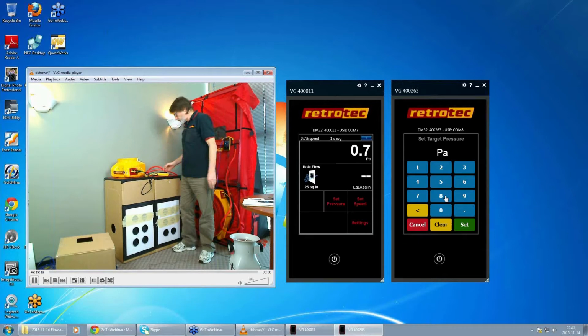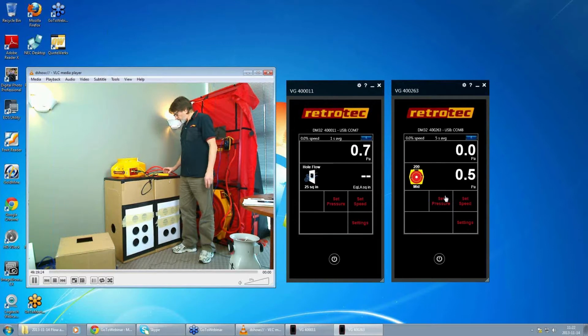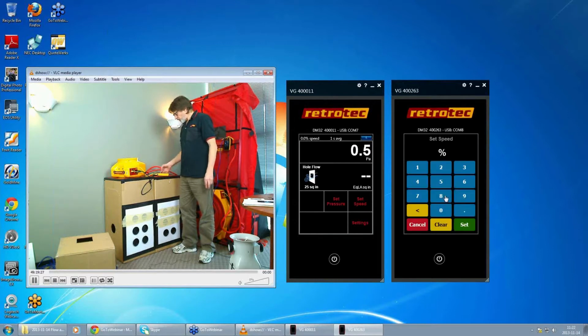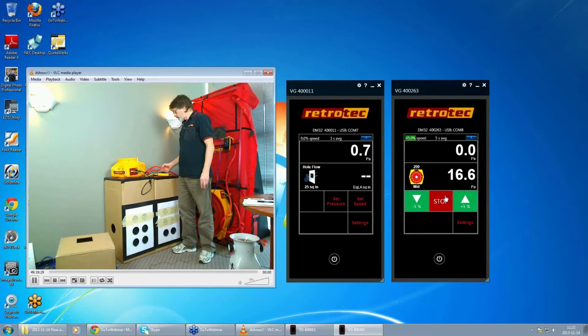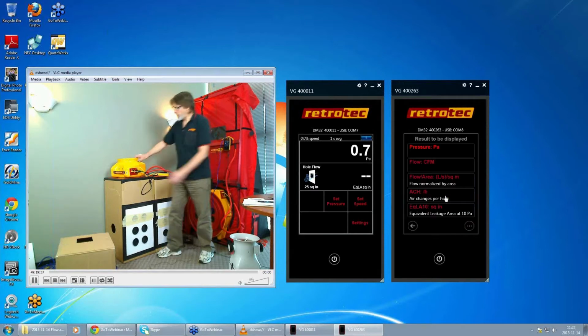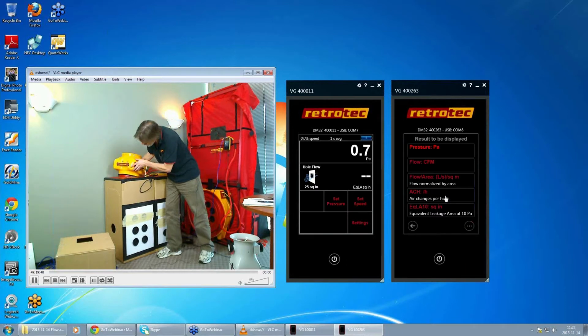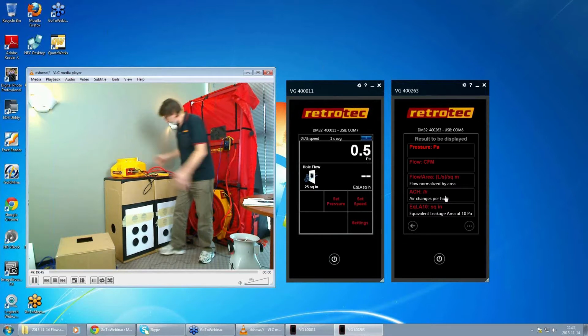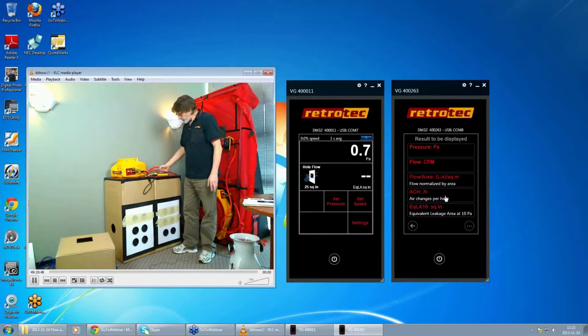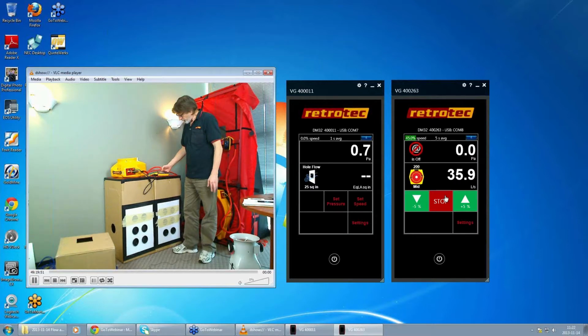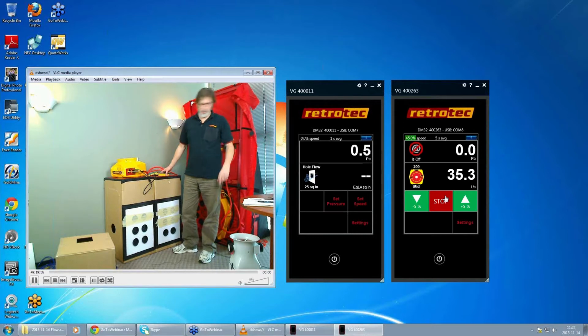Okay, so here I'm going to set the speed. I'm just going to set it to about 45%. And I'm going to change this to, you can't see this, but this duct tester here is on the mid-range. So it's going to plop it back in there. So I'm going to measure flow in CFM. I'm set to the mid-range on the right-hand gauge.